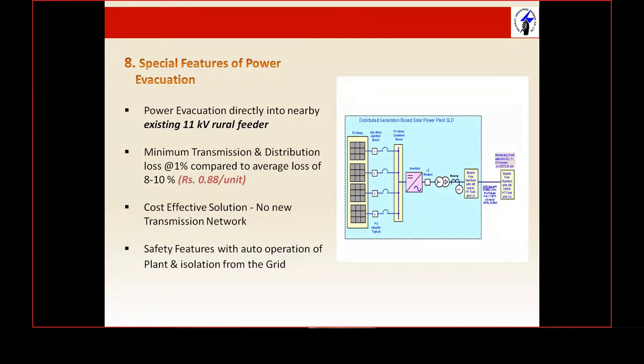The problem here is the rural feeder. Even in Gujarat there are almost 7 to 8 trippings in a day in some areas, because these are very large feeders, maybe 15-20 kilometers long. Whenever there's a bird fall, a tree falling, or some weather-related issue, 11 kV feeders get tripped, or sometimes due to power curtailment by the discoms. All these jerks are absorbed by the solar plant with no detrimental effect whatsoever over the last 3-4 years. That's our experience with the 11 kV rural feeder.